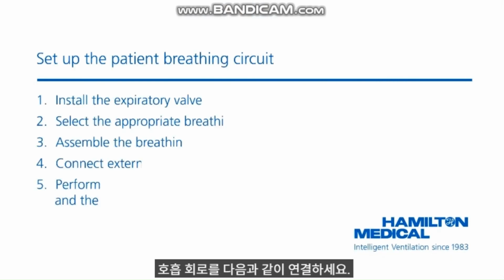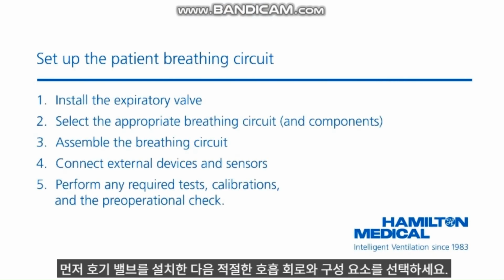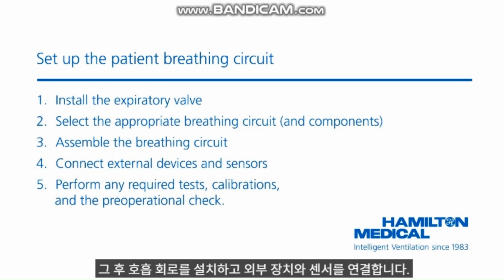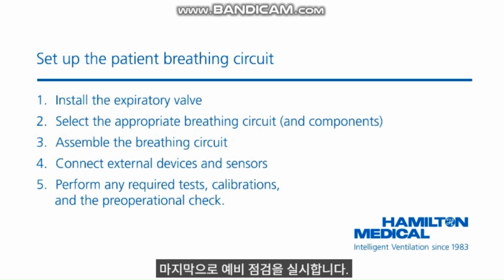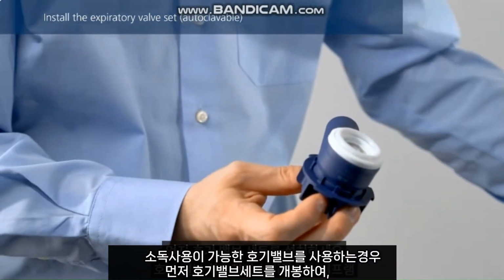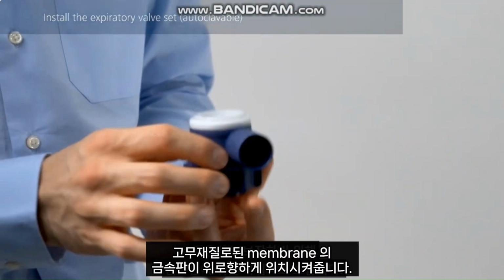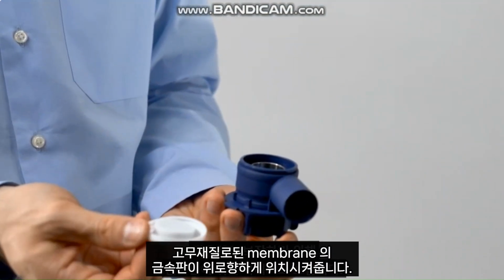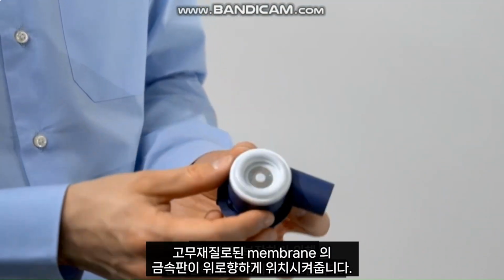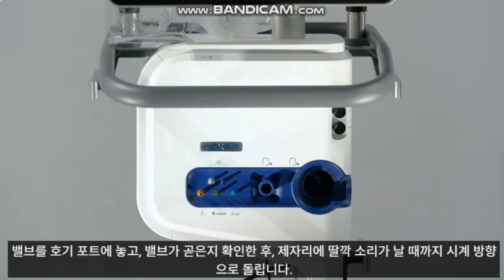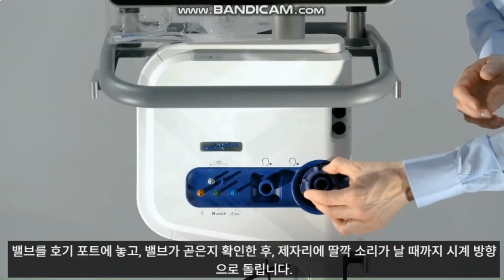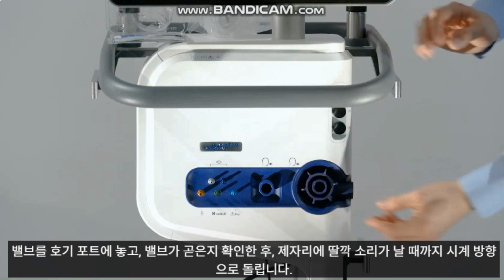To connect the breathing circuit, do the following. First, install the expiratory valve. Then select the appropriate breathing circuit and components. Third, assemble the breathing circuit. Then connect the external devices and sensors. Perform the pre-operational checks. First, assemble the expiratory valve set by placing the silicone membrane onto the expiratory valve housing. Ensure that the metal plate is facing upwards and is visible. Position the valve in the expiratory port, ensuring it is straight, and twist it clockwise until it locks into place.